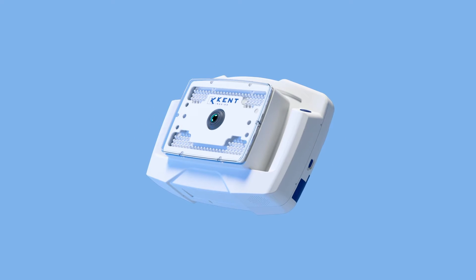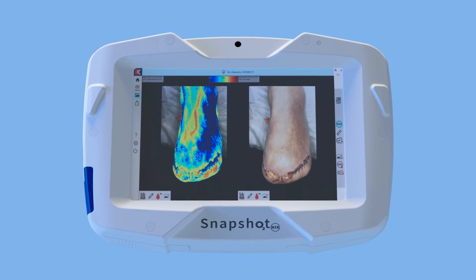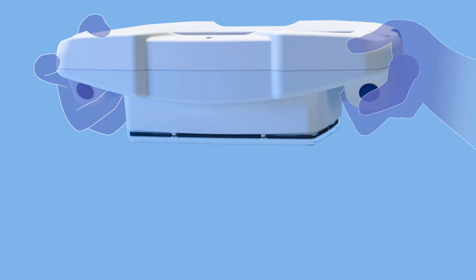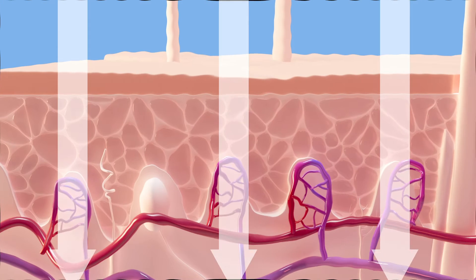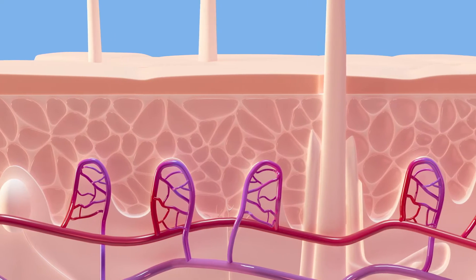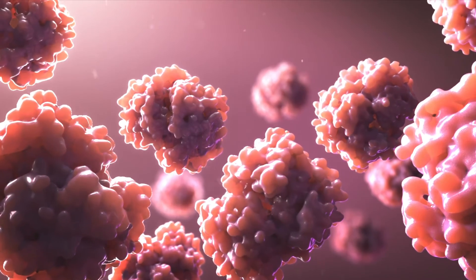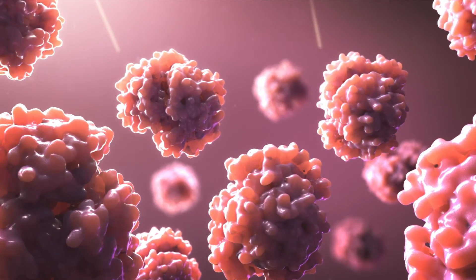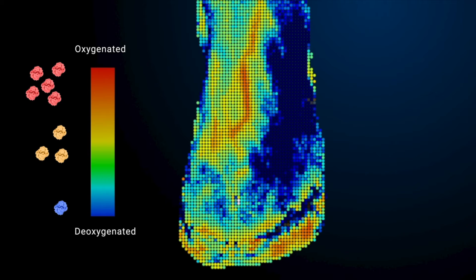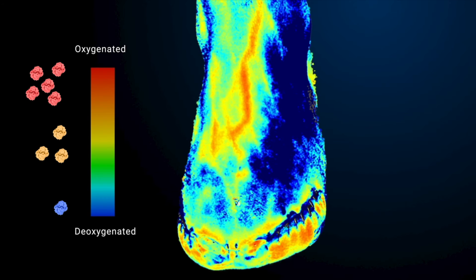Snapshot NIR is an imaging device that visualizes and maps tissue oxygen saturation in the capillary network. It flashes six near-infrared electromagnetic wavelengths of light for about one millisecond. These predetermined wavelengths of known light illuminate the tissue and are absorbed differently by the variations in the electron clouds of the oxygenated and deoxygenated hemoglobin molecules. The light that is not absorbed is reflected and measured by the Snapshot NIR device. A patented algorithm assesses oxy and deoxy hemoglobin levels to determine the oxygen saturation at each image pixel of the return signal. A tissue oxygenation map is displayed within a matter of seconds.